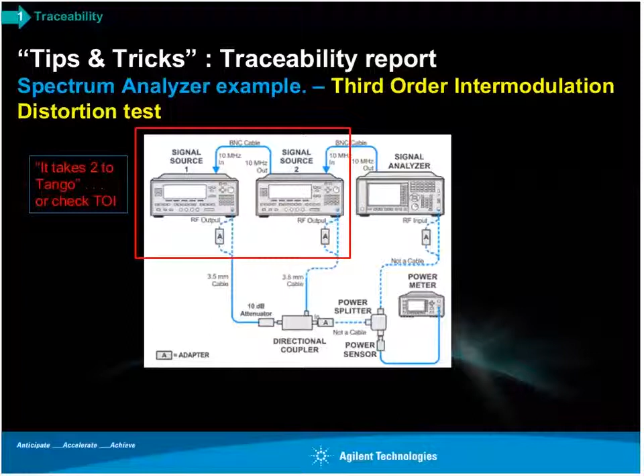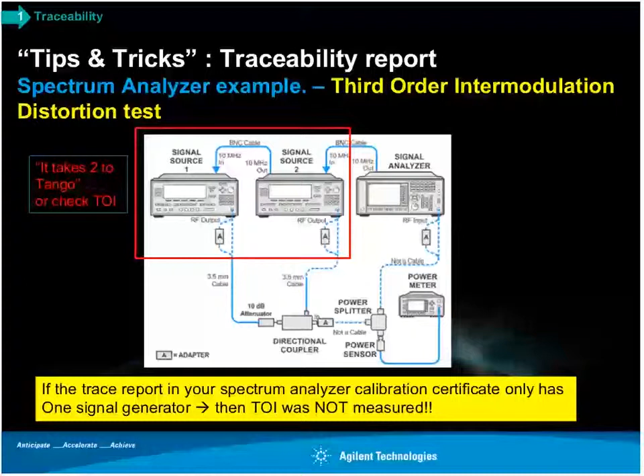In any case, what I wanted to show you is this. That particular test takes two signal generators. Just like the old expression, it takes two to tango, similarly, it takes two signal generators to check TOI. I've seen this before, by the way. If you see a trace report on the spectrum analyzer calibration certificate and there's only one signal generator, then you know that third-order intermodulation was not measured. To me, as an engineer, that's a giant red flag because I can't trust some of my favorite measurements that I like to make with spectrum analyzers. So there's a couple of ways that you can look through just the list of instruments to see what was done.